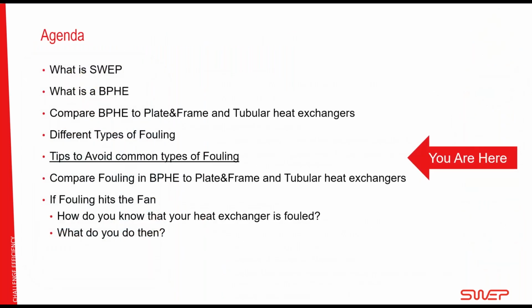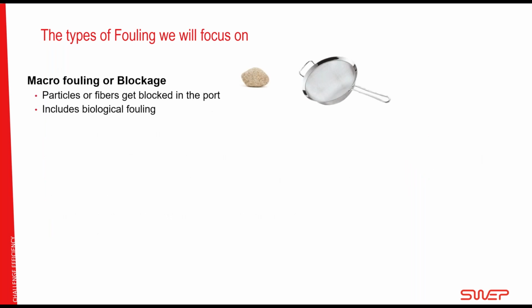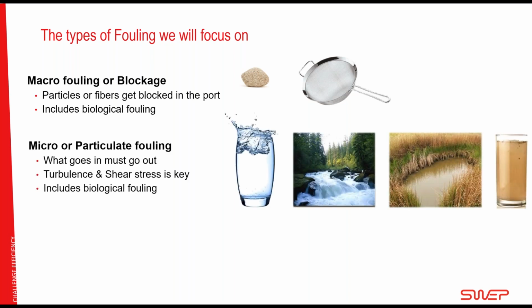That was it. So let's go into depth. Now we are looking at tips to avoid common types of fouling, the in-depth method. So what will we focus on today? Well, I already mentioned macrofouling or blockage, when particles and fibers get blocked in the port. Think of it as a stone getting swept up by a sieve, and make sure that you have a sieve so you don't have to use the heat exchanger as the sieve. Then micro or particulate fouling: whatever comes into the heat exchanger must go out. Turbulence and shear stress are key to make that happen.